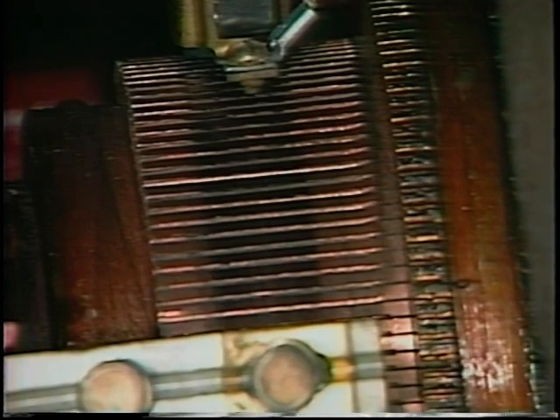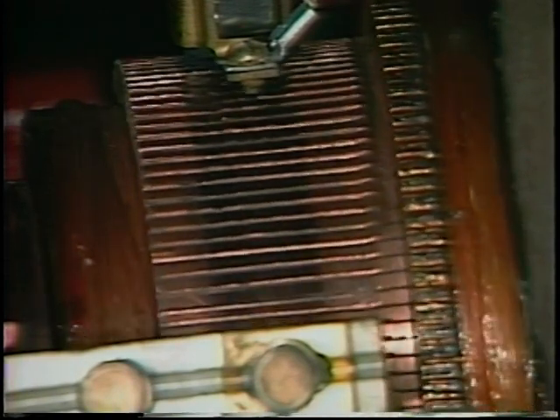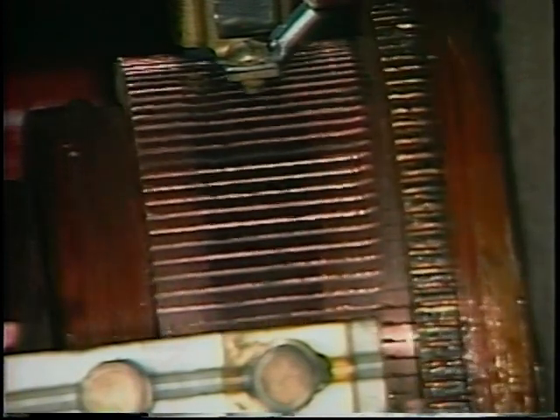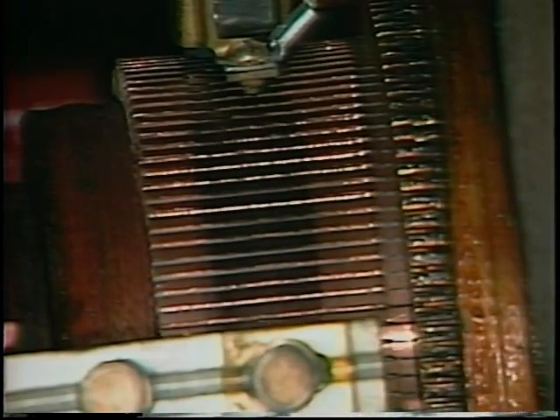Practically anything that interferes with good electrical contact will make the brushes spark. The commutator must be smooth. If the motor has been running normally and under load, it will have a brown glaze. Grooves or ridges, burning or pitting of the bars, or high mica between the bars all require motor disassembly and repair.